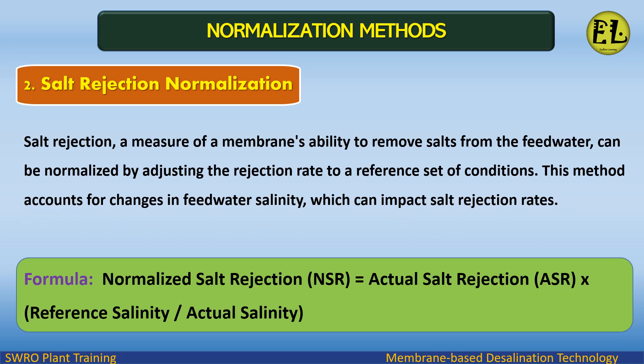Salt rejection normalization: salt rejection — a measure of a membrane's ability to remove salts from the feed water — can be normalized by adjusting the rejection rate to a reference set of conditions. This method accounts for changes in feed water salinity, which can impact salt rejection rates. The formula is: Normalized Salt Rejection (NSR) = Actual Salt Rejection (ASR) × (Reference Salinity / Actual Salinity).